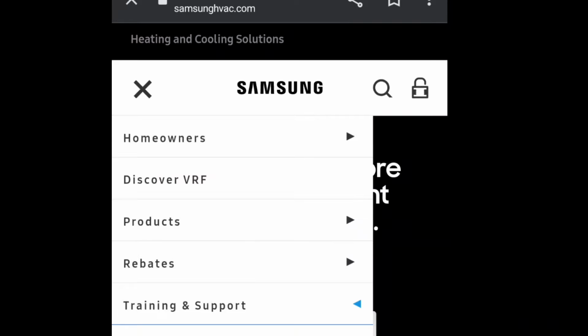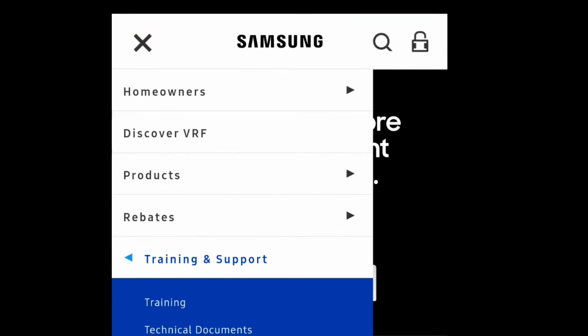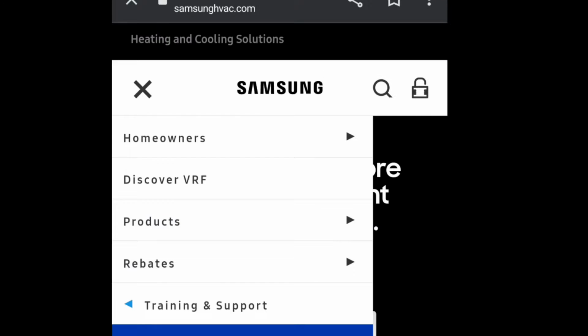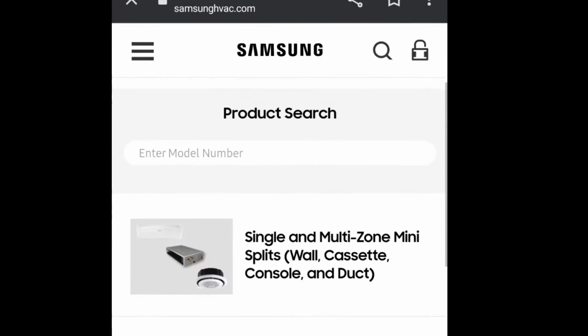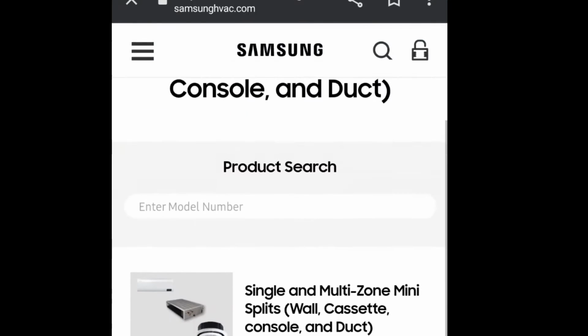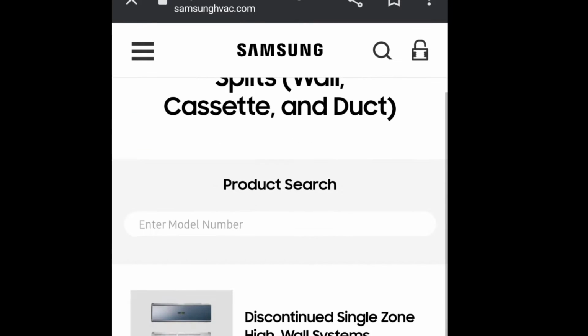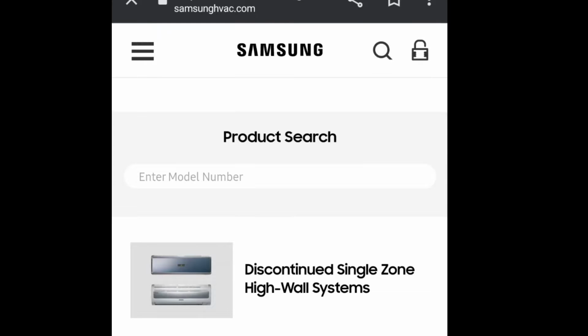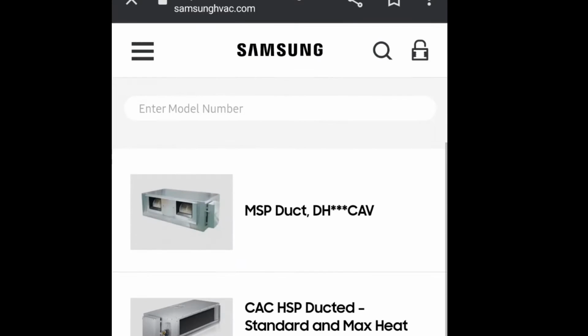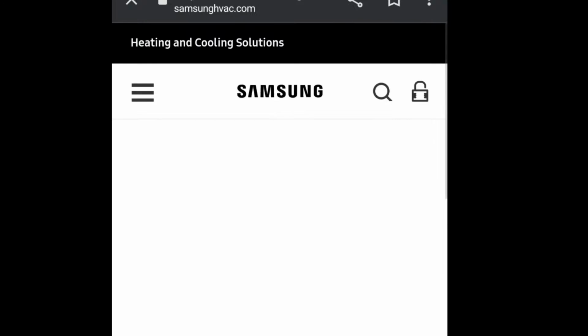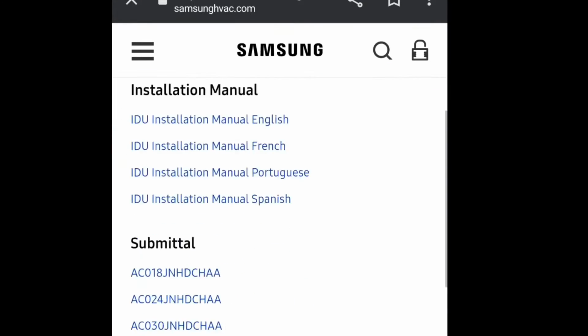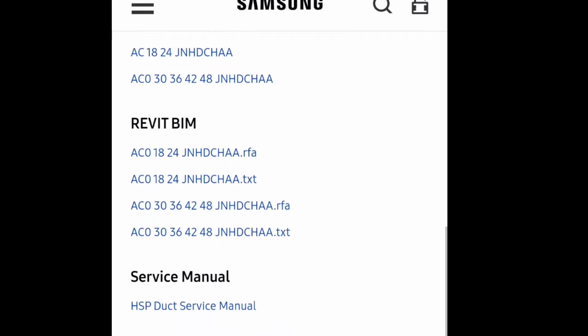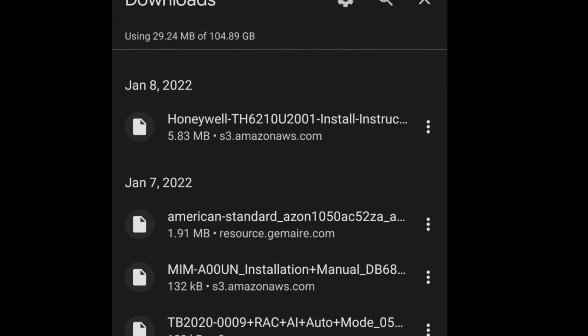So type in Samsung HVAC in your search bar, and then we're going to click top left-hand corner, those three bars. We're going to go to training and support, and then technical documents. Oh, that's technical videos. We don't need technical videos. We need technical documents. Now we scroll down, go to single and multi-zone units, discontinued, because this is an older air handler. We're going to go to the discontinued single zone duct system. Now we're looking at the high static pressure ducted air handler, and we're going to scroll down to where it says HSP duct service manual. I've already got this downloaded, so I'm just basically going to go here and click on the service manual.